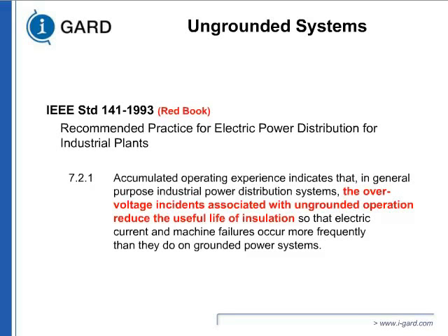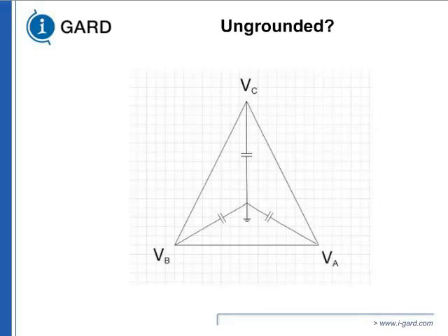In the true sense, if there are some electrical engineers in the audience, they will know and they will claim there's nothing in this universe that is ungrounded. An electrical system cannot be ungrounded. It's always capacitively coupled to the ground. That's the reason in the second slide I told you to keep an eye on "intentionally grounded." So every system has a capacitive coupling. That's where the arcing starts. So keep that in mind. When we say ungrounded, we mean it's not intentionally grounded. But every system in this universe is capacitively coupled.